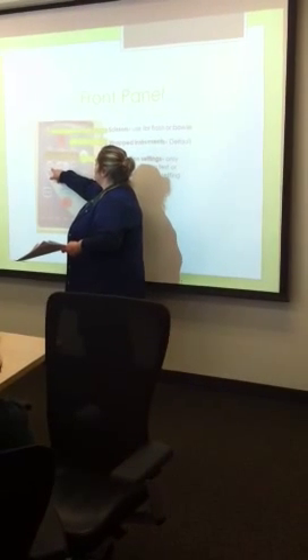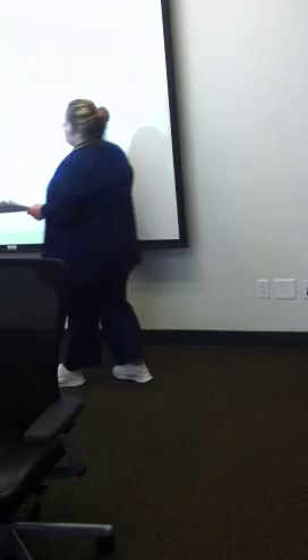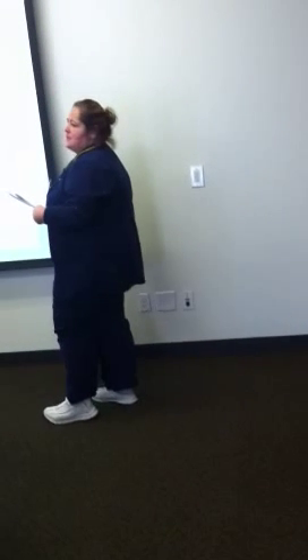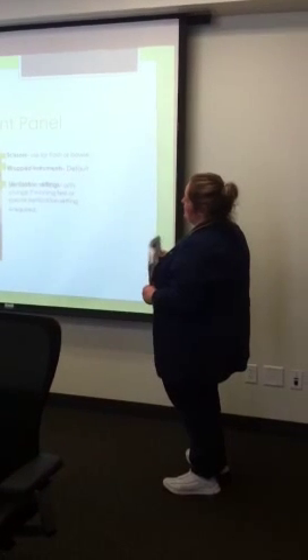This here is your sterilization settings. Make sure that when you come in, the temperature should always be 273, your steam time should be 8 minutes, and your dry time should be 30 minutes. The only one who really would be changing that would be myself if I'm doing the maintenance on it, as well as Leslie, because she's the backup. So we would change that when we run the Bowie Dick test and when we run the spore testing, we would change those times.